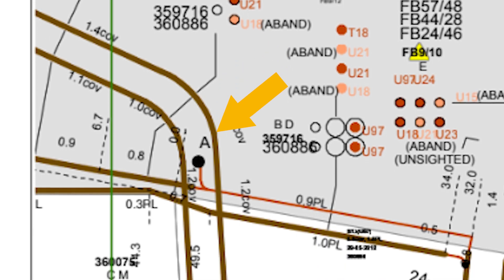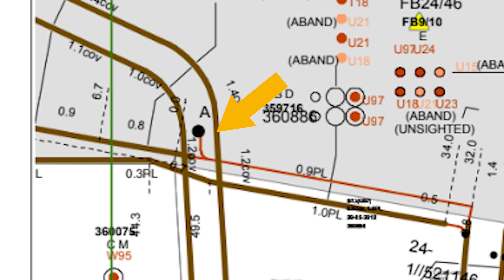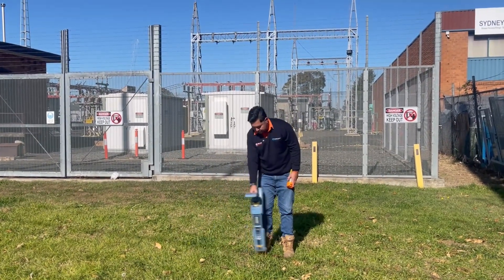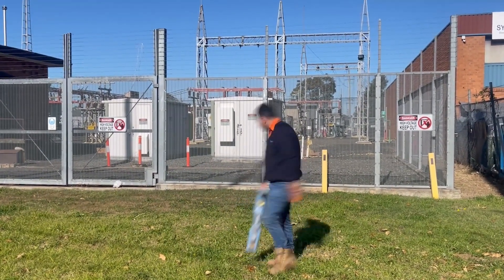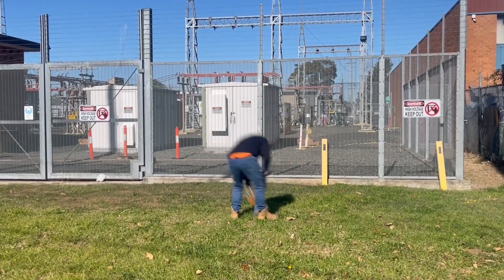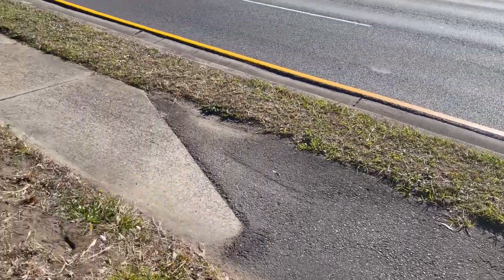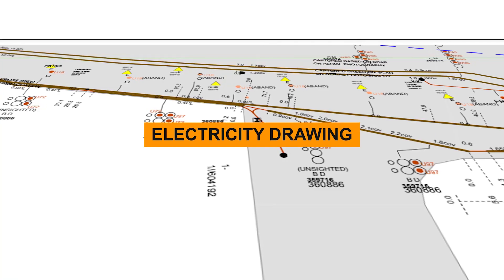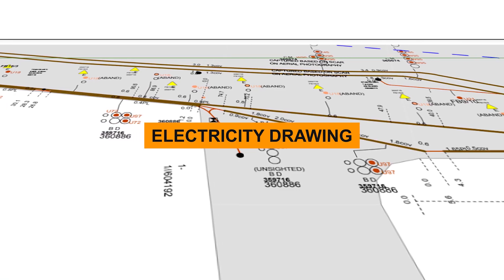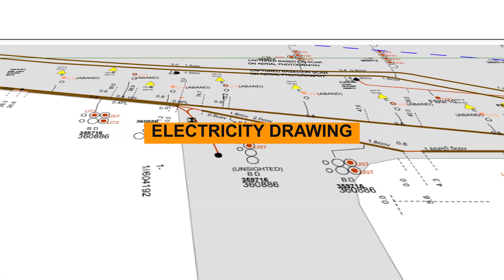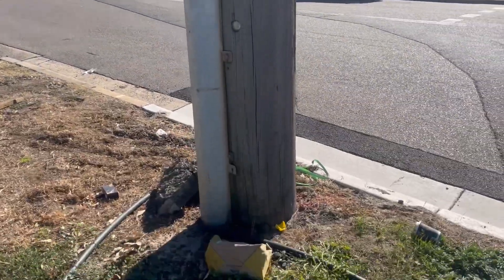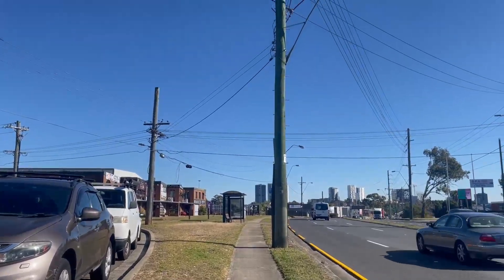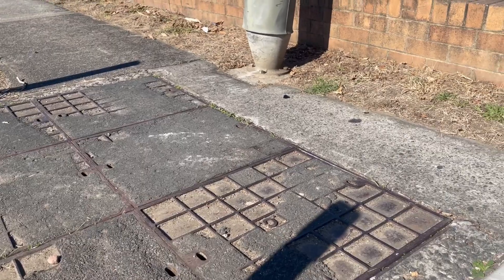Let's have a quick look at this Endeavour Energy electricity substation here in southwestern Sydney. As you can see on the plan, there are some high voltage conduits running through the road and bending into this substation. These are the cables I'm going to sweep over using the power mode on this Radio Detection receiver. I know that there are cables coming in roughly to the western side of this substation from the available electricity drawings.